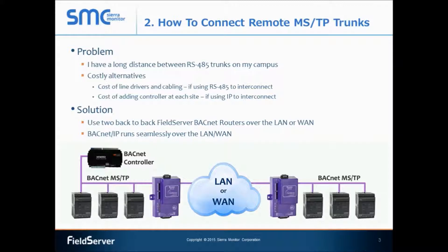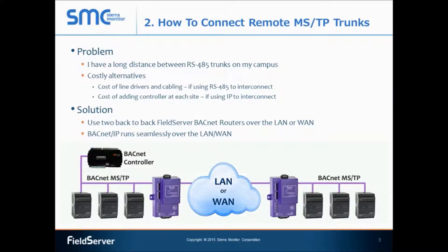By installing and configuring a BACnet router from BACnet MSTP to BACnet IP, and a second router back-to-back from BACnet IP to BACnet MSTP, I can get the BACnet MSTP network up and running very quickly, keeping my installation and commissioning costs as low as possible. The IP protocol runs over the LAN or WAN depending on the physical locations of the buildings.